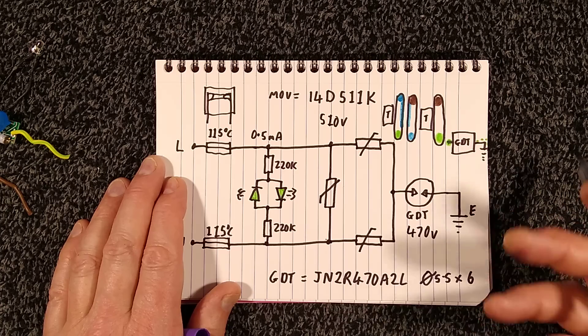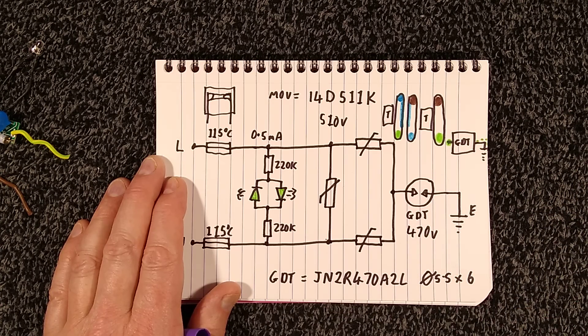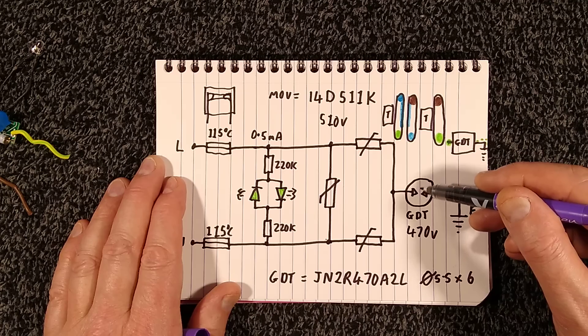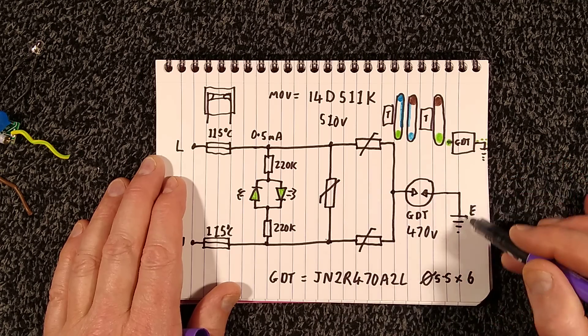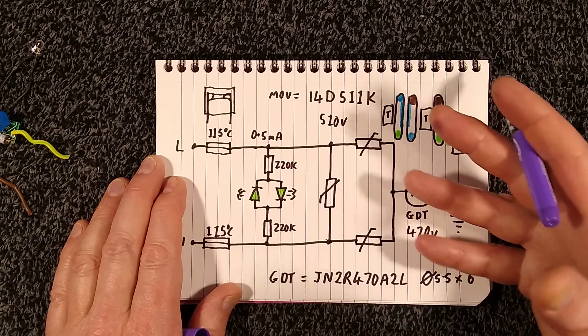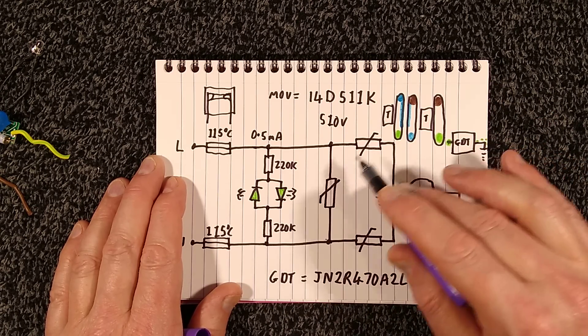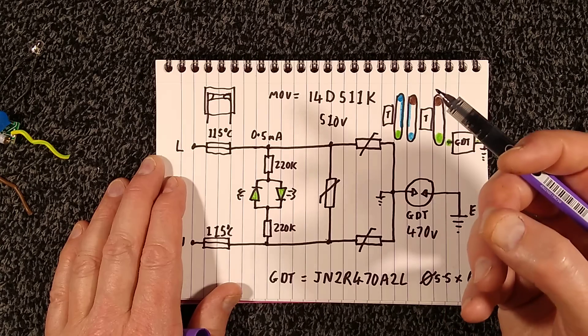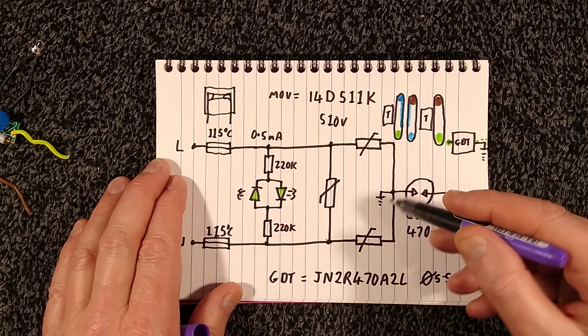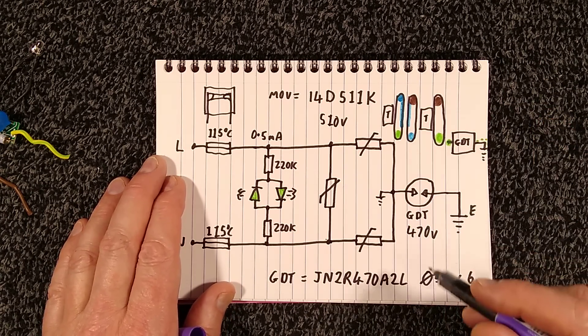And that provides that gap between these and earth because some of these surge devices simply have the earth connected here. And what that means is that as these fail, you can get increasing current flowing to earth and it means that if the earth goes open circuit somewhere, it poses a shock risk.